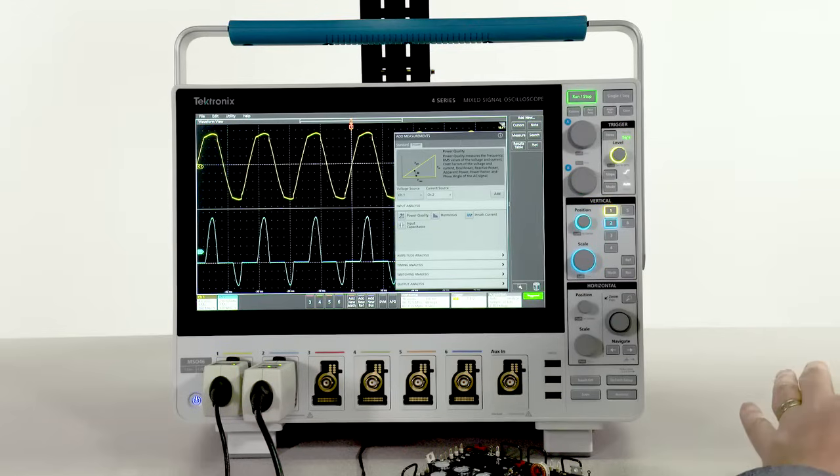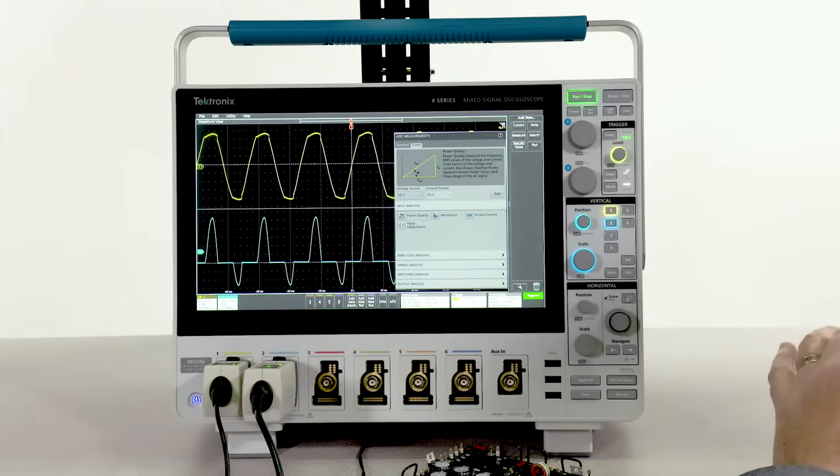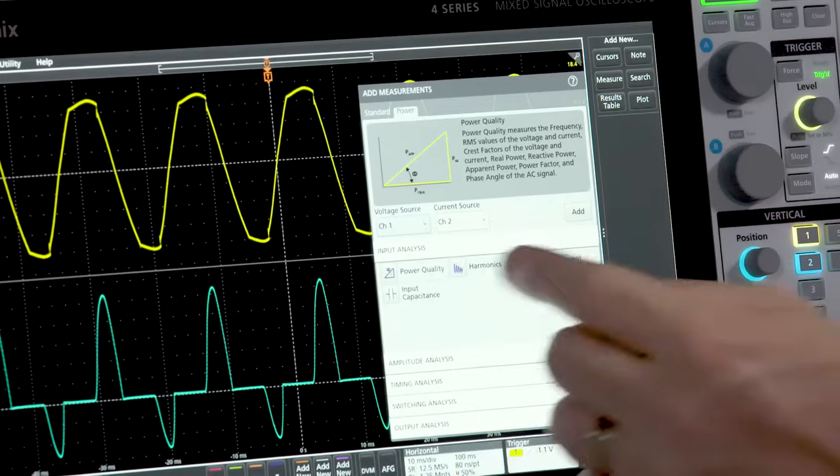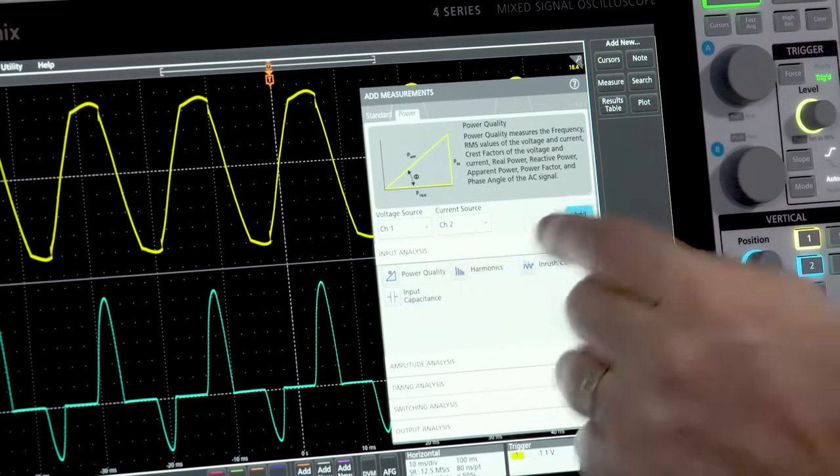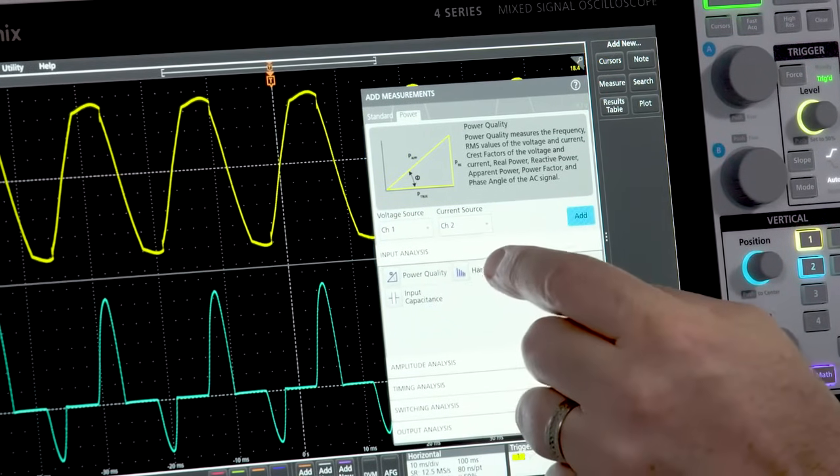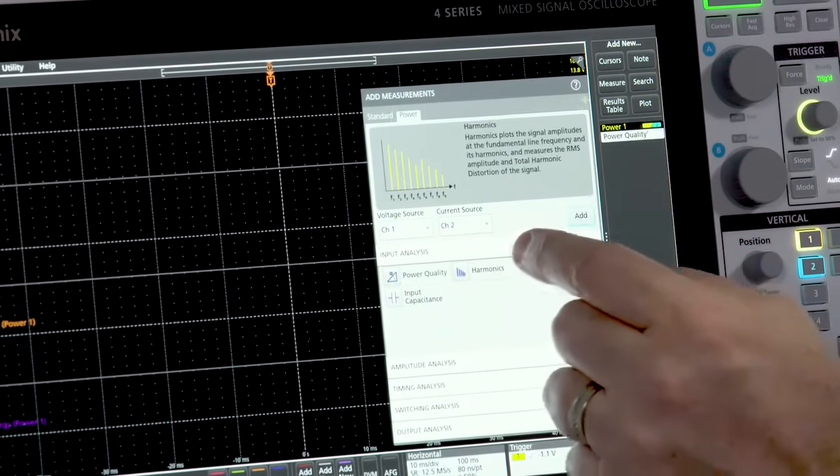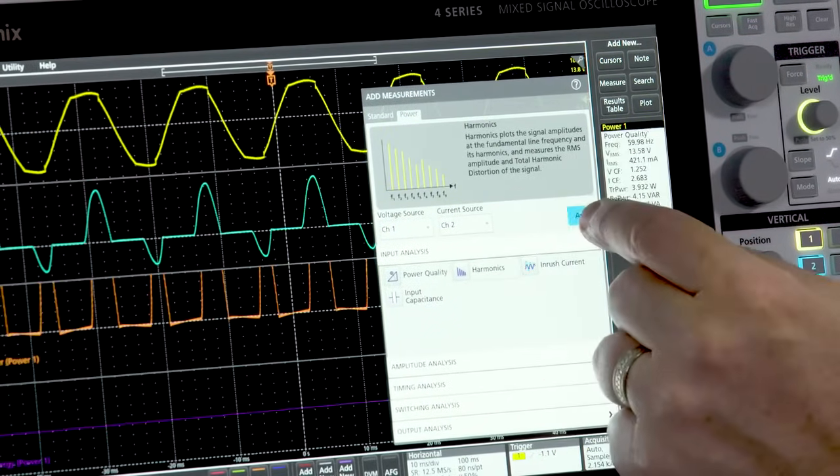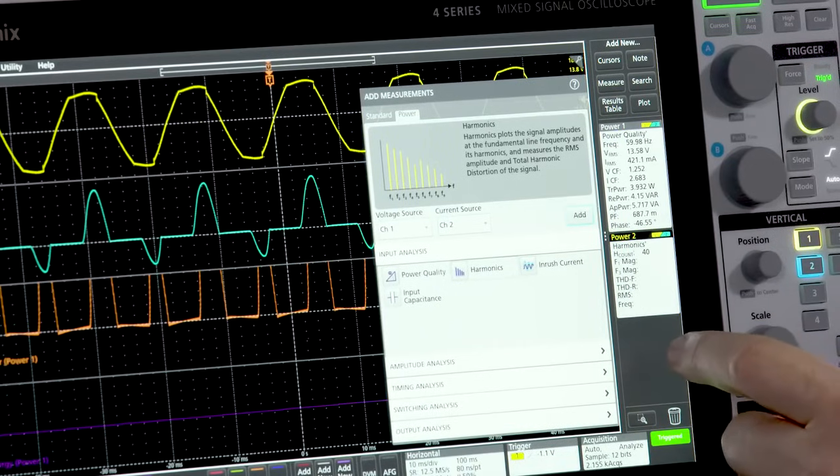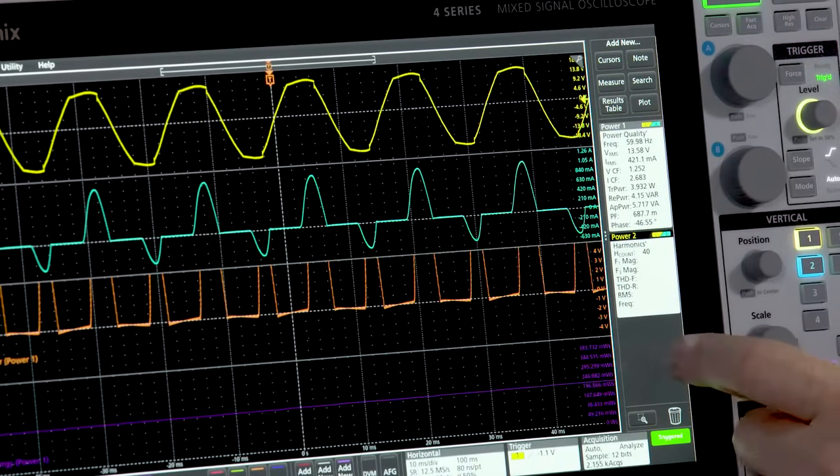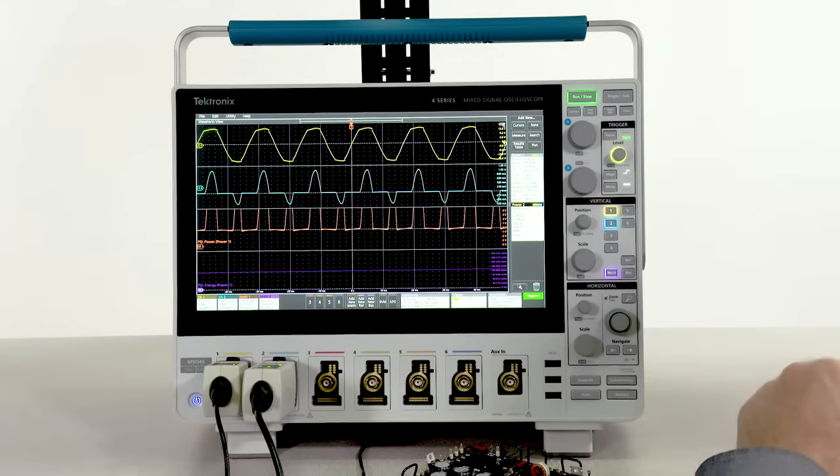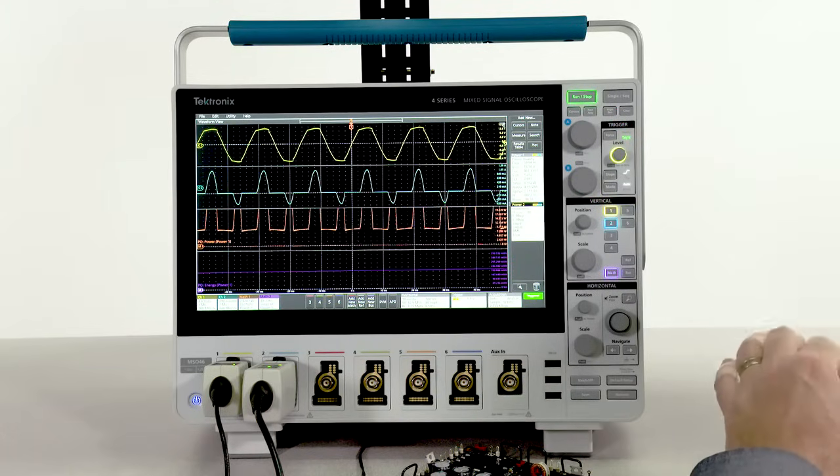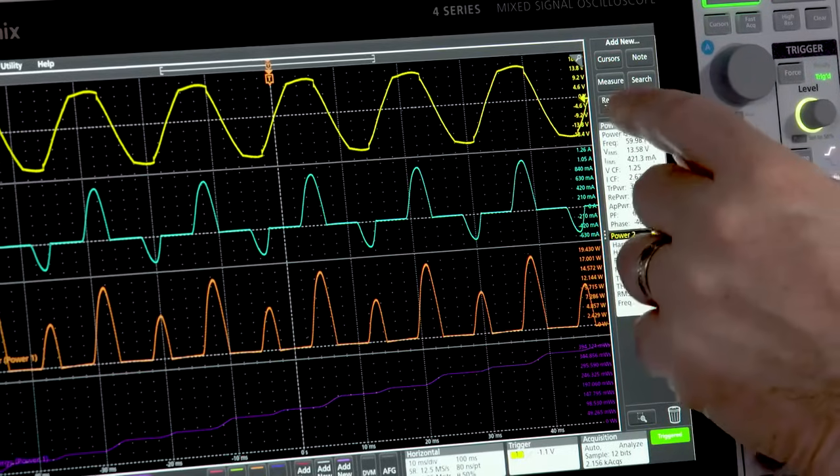Quickly take AC line measurements like power, apparent power, and power factor. You can get all these important measurements along with means and standard deviations in a results table.